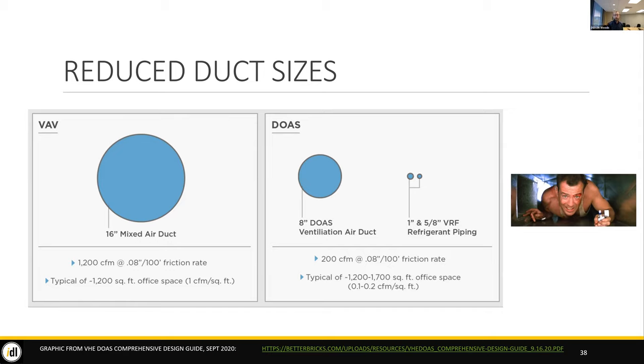And this is going to really limit our plenum requirements and floor to ceiling. And where I think savings are often missed is from a design standpoint. If you no longer have to design for this extra plenum space, that doesn't just mean that your floor to ceiling is going to get a little bit higher. It means if you're at the very beginning of the design process, the building itself can be a little bit shorter. So imagine all the savings that can come from that extra 6 to 12 inches of height, all that extra masonry, the extra height on the windows or spandrels, whatever have you. That is going to be a major savings.